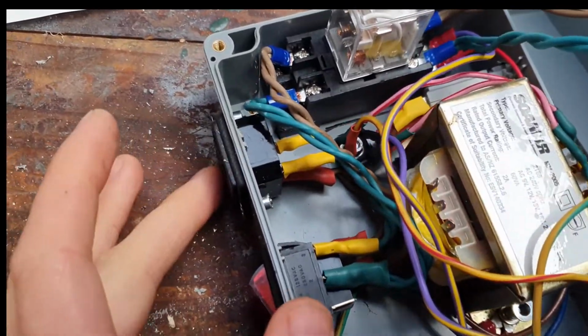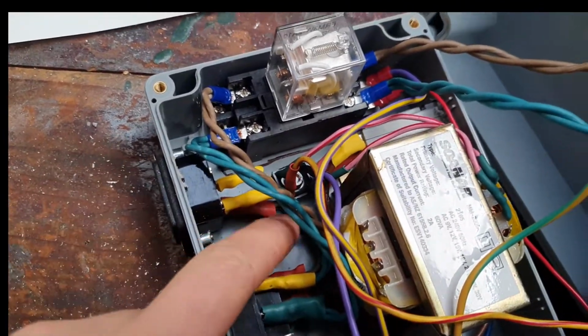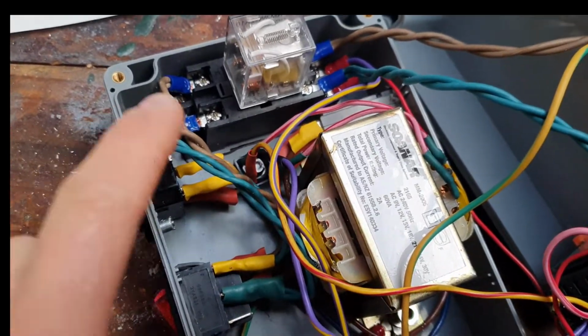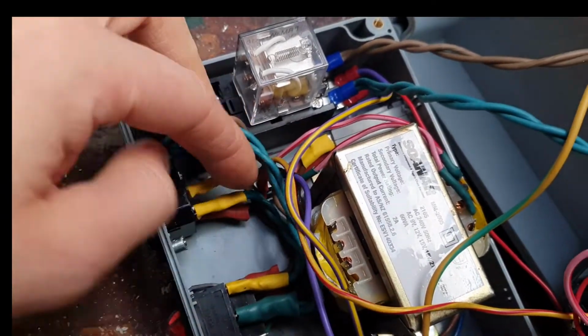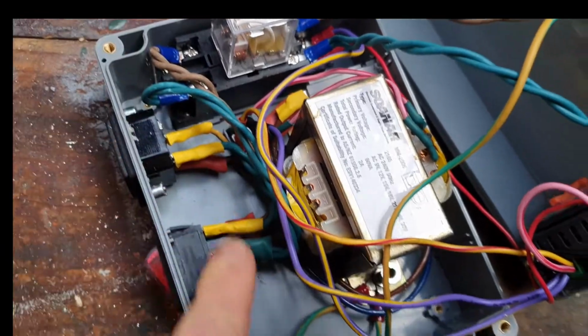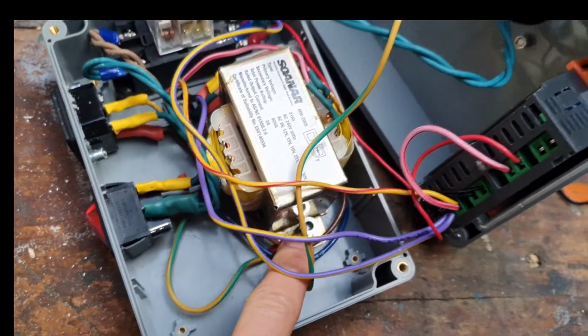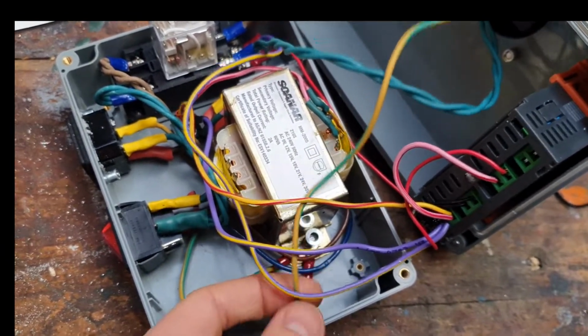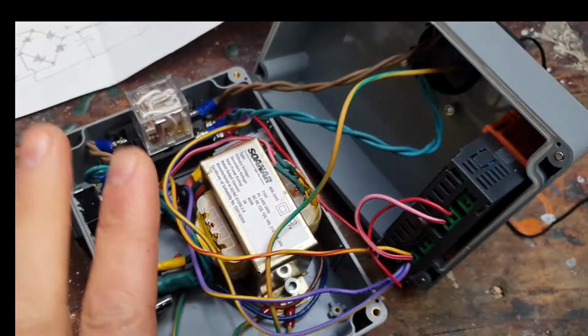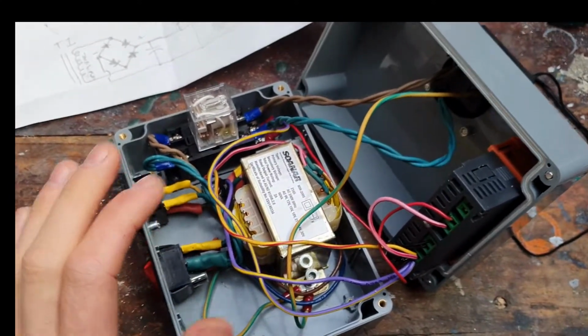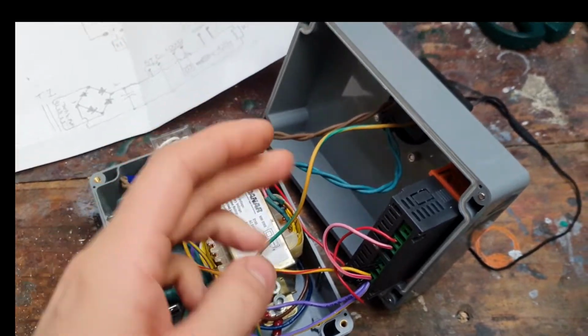Basically what we've got is the power coming in through the IEC connector, going straight to the on-off switch. I have also connected through the earth pin of the IEC connector on this green and yellow wire to the case of the contactor, and then through to the output socket. It's very important for safety that you connect through the earth wire to the output socket.